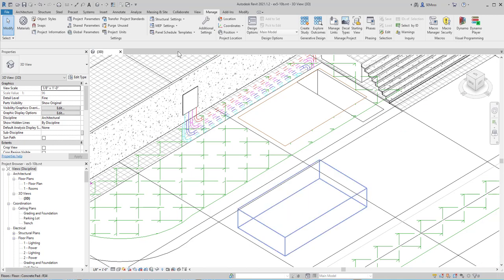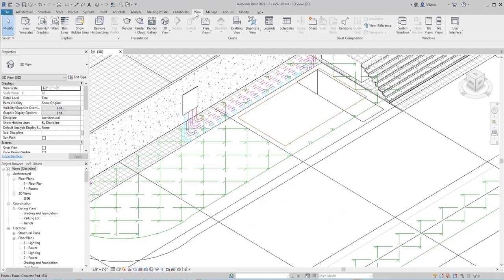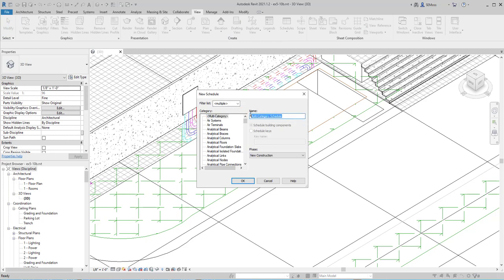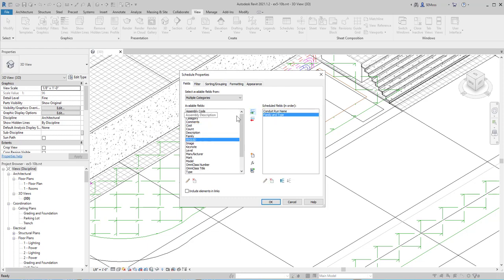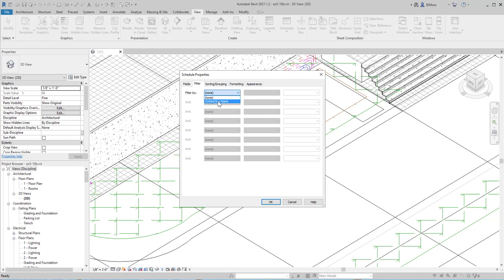Now we can go about creating our schedules. I'm going to go to the View tab on the ribbon, go to Schedules, Schedule Quantities. I'm going to select Multi-Category and call it Conduit Runs. What I'm doing here is trying to locate any conduit that hasn't been assigned a conduit run name. I'll say OK, then select Conduit Run Name, Family, and Type as fields. Then I'm going to go to the Filter tab and say Conduit Run Name has no value — this will search through the model and locate any conduits that don't have a conduit run name assigned.